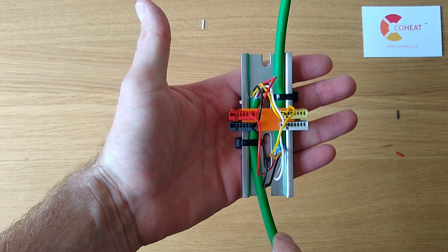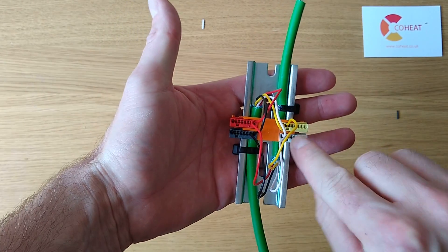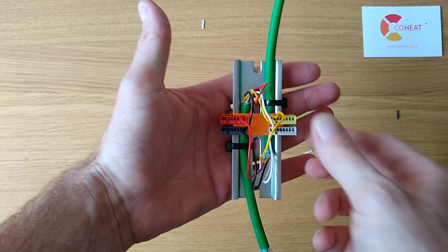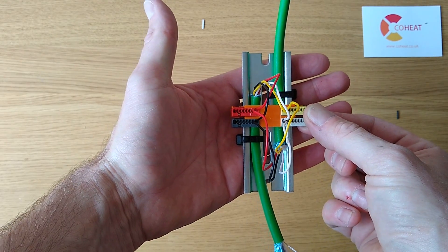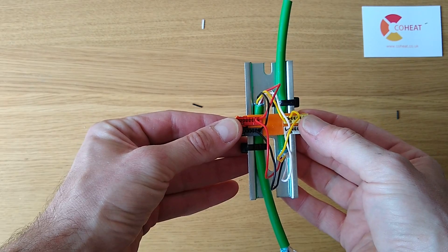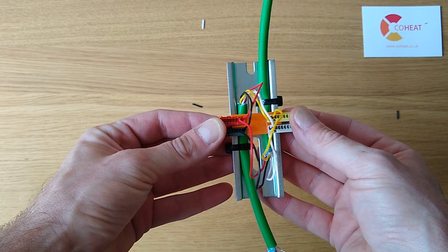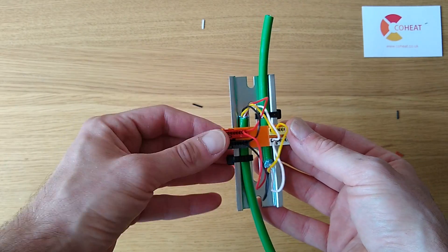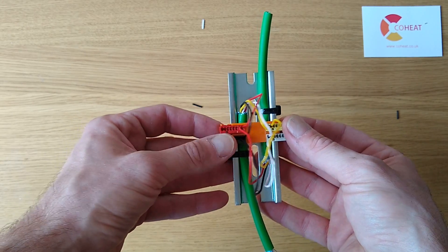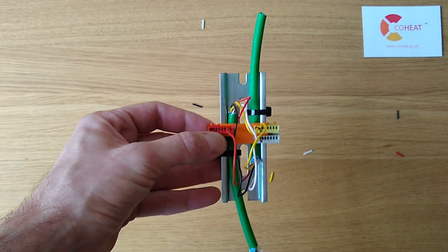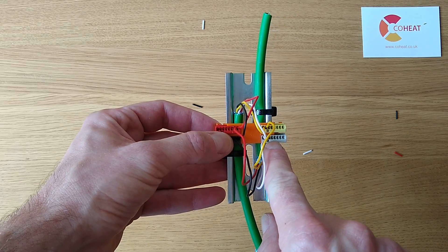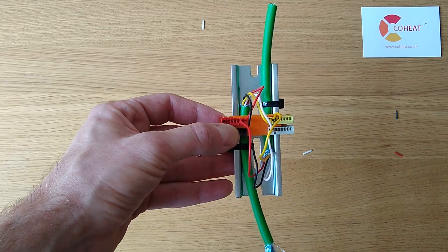This makes it easy to test if we have voltage here and here. For example, yellow and white being MBUS, red and black either being a Modbus link to electronic HIUs, or 24 volts for remote differential pressure sensors and whatnot. If we need to, you can twist these and remove them. And you have a bunch more ports available for connecting HIUs coming from the laterals.